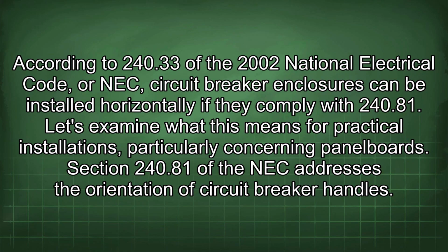According to 240.33 of the 2002 National Electrical Code, or NEC, circuit breaker enclosures can be installed horizontally if they comply with 240.81. Let's examine what this means for practical installations, particularly concerning panel boards. Section 240.81 of the NEC addresses the orientation of circuit breaker handles.